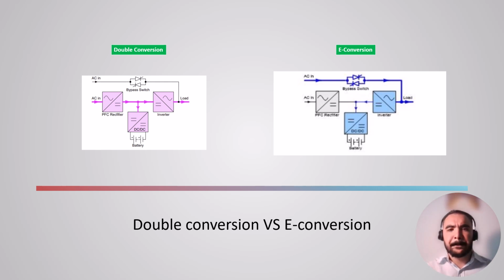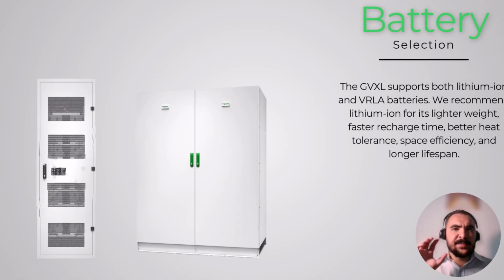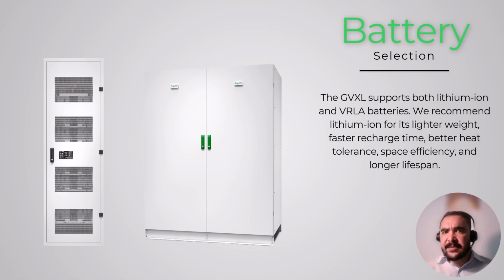Speaking of batteries, battery flexibility to suit your needs and wants. The Galaxy VXL UPS is flexible in battery selection, allowing you to choose between VRLA batteries and lithium-ion batteries. However, although both battery systems are supported with the Galaxy VXL UPS, we highly recommend lithium-ion for its superior advantages, like lighter weight for easier handling and installation, heat tolerance with less cooling needed, faster recharge time for improved availability, longer lifespan for greater value over time, and finally a space-saving design, as the batteries take up less room.